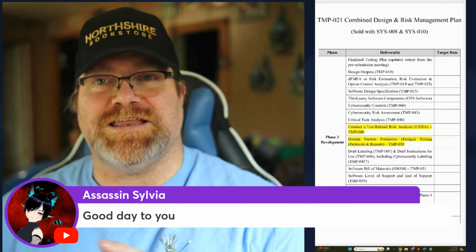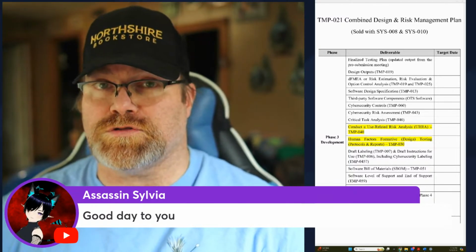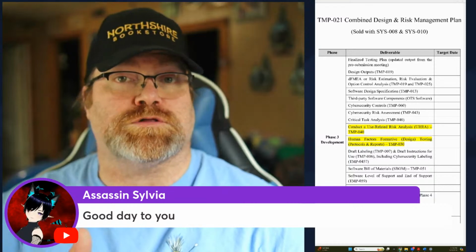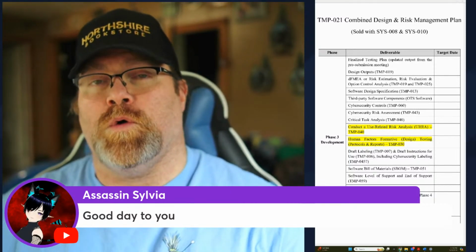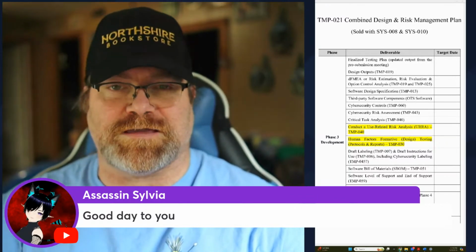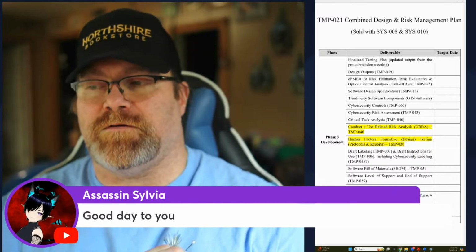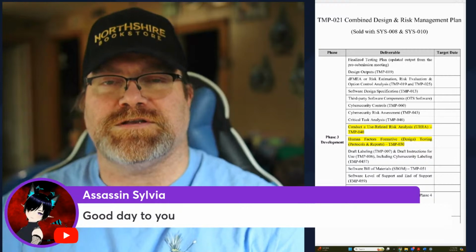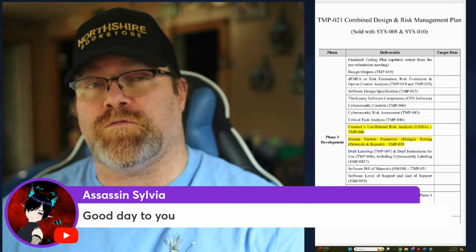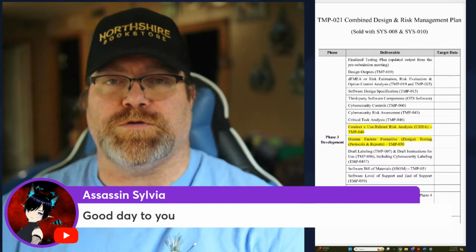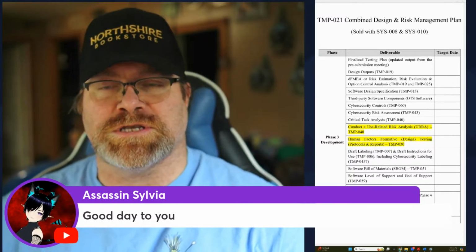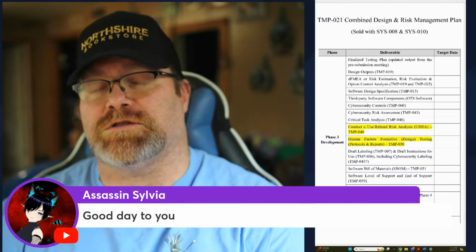You also might be looking at different versions of user interfaces and different risk controls that you want to try. See which one is the easiest, see which one leads to the fewest mistakes, see which one is the most precise, if accuracy is important. So when you're trying to develop different risk controls, that's a perfect reason for doing small formative testing. So you might have multiple human factors formative testing 1, 2, 3, each for a different purpose. There's no required format, there's no required content, but the more formal you make it, the easier it will be able to document in your usability engineering file how those results from your formative testing resulted in design changes, and that'll help you because that's required actually in your summative report.